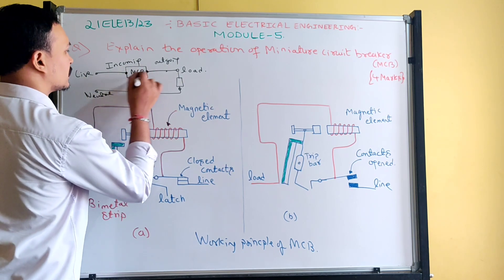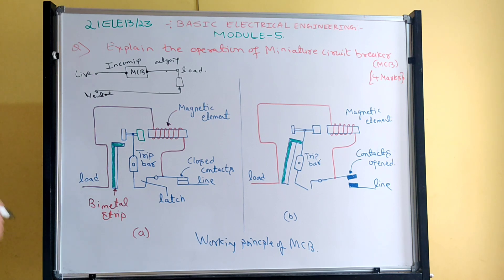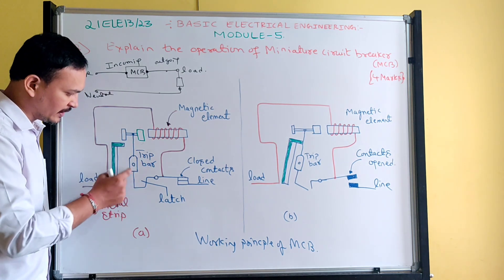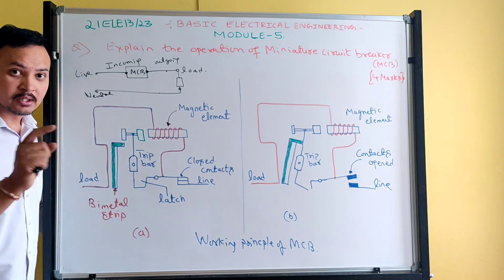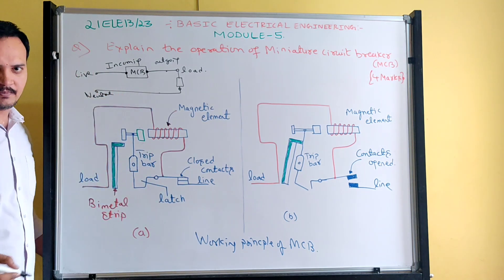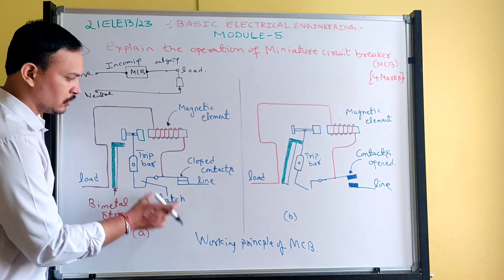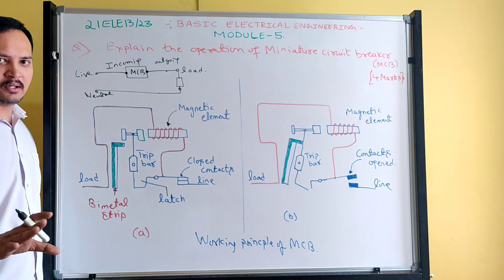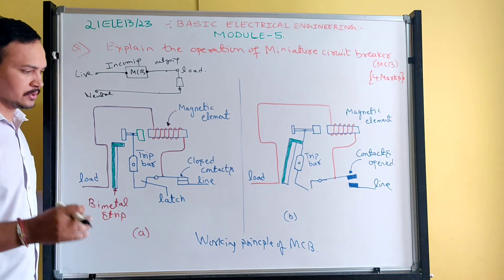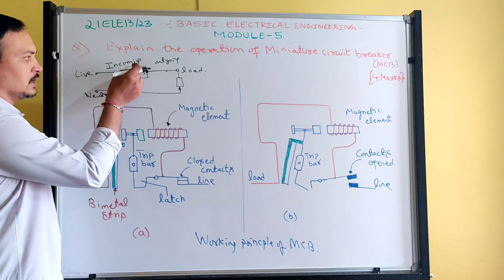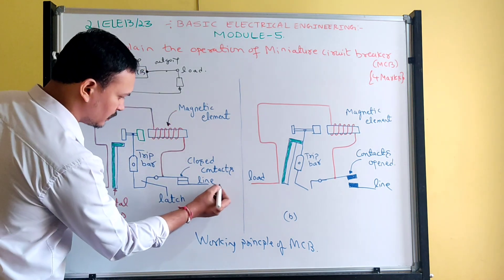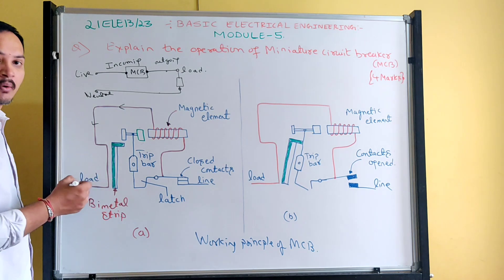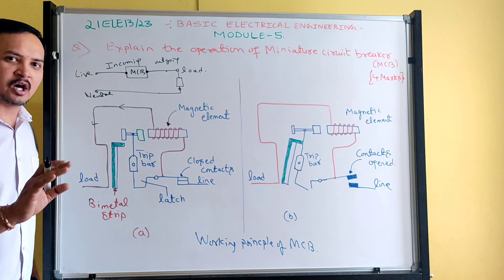Now, actual working — what happens. This is called the bimetallic strip, and this is the trip bar. The trip bar is connected to the latch. The latch is the heart of the MCB — this is very very important. Without this, the contacts will not open and close. Figure A is normal condition — no fault, no overload, no short circuit. Under that condition, contacts are closed. Once I close the contact of MCB, supply gets connected, and current passes through the magnetic coil. Load will get continuous supply under normal condition.